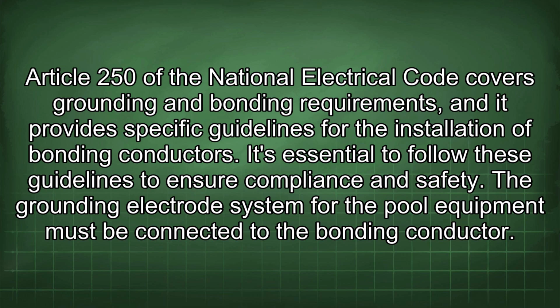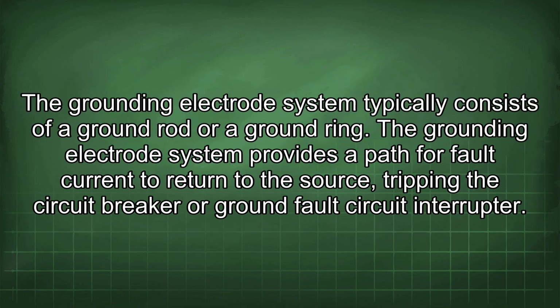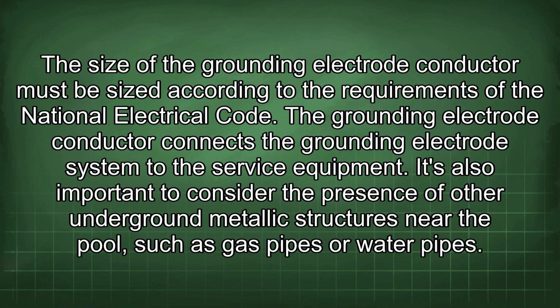It's essential to follow these guidelines to ensure compliance and safety. The grounding electrode system for the pool equipment must be connected to the bonding conductor. The grounding electrode system typically consists of a ground rod or a ground ring. It provides a path for fault current to return to the source, tripping the circuit breaker or ground fault circuit interrupter. The grounding electrode conductor must be sized according to the requirements of the National Electrical Code. It connects the grounding electrode system to the service equipment.